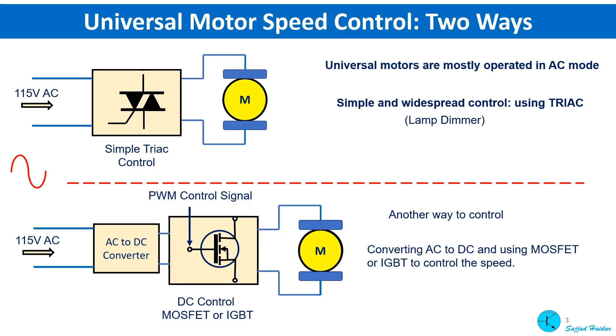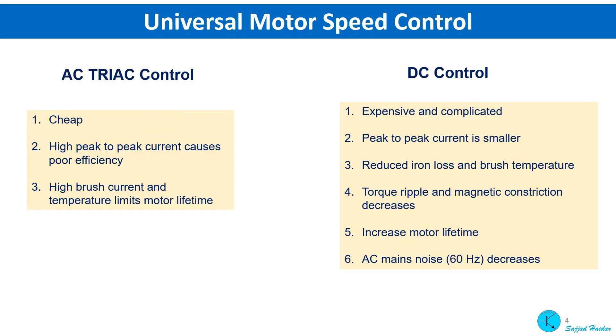One way of controlling the speed is to use a simple lamp dimmer, which uses a semiconductor device called a TRIAC. The other way is to convert from AC to DC first, and then using a power semiconductor device — either a MOSFET or IGBT — control the speed of the motor. A PWM signal, or pulse width modulated signal, is applied to the gate. There are advantages and disadvantages to both control circuits.